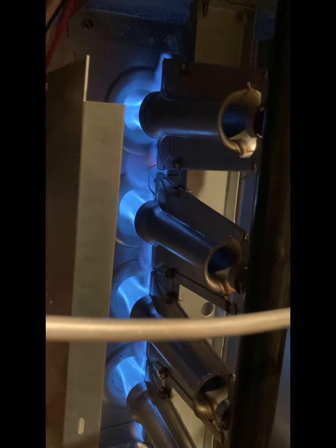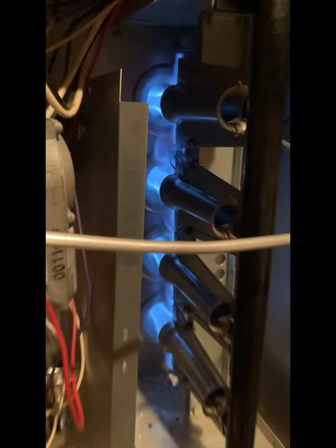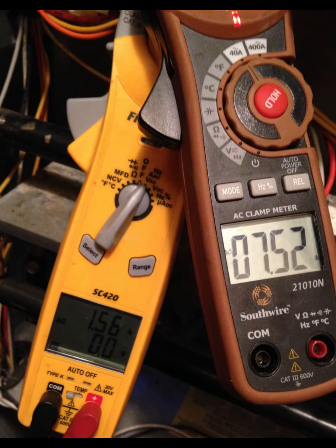We can pull that flame sensor out. It's typically a 1/4-inch screw. Pull that flame sensor out and clean that thing. Use an emery cloth. And I know the gangsters like to use the dollar bill. I know men like to use a $100 bill to clean it. Whatever. Emery cloth it up. Get it clean. Plug it back in. And once that flame sensor proves that it has a signal, the flame's going to stay on for you.